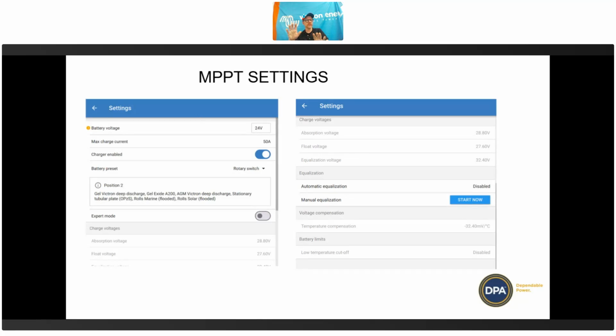Wire up your system, turn on your battery first, don't turn on the array, and then set the battery voltage to whatever your nominal battery voltage is. The max charge current, you're not normally going to adjust this unless you want to throttle the array for some reason. And then charger enabled, yep, you probably want it to be enabled most of the time.